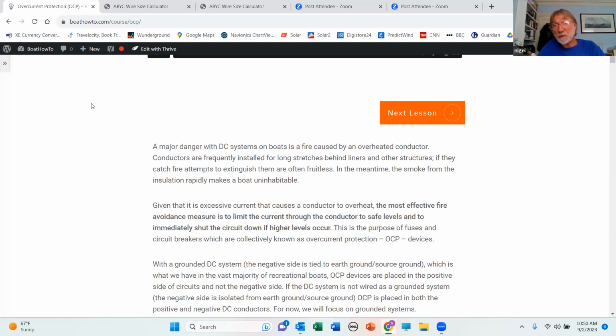But now it's in an engine room, which we know is going to be hot when the alternator is running, because the engine has to be running. And we may strap it up with the negative conductor, so now it's bundled. We've got a bundle of 2 to 3. We discover that we have to derate that 2-aught conductor down to maybe 280 amps. And we've got an alternator that can put out 360 amps.